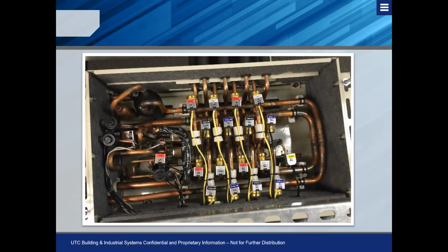If it's something that's caught up in the solenoid, not operating properly from the internals, that's a different story. But if you have an issue with that coil trying to open or close that solenoid, all it is taking is one Phillips screw here, taking that off, lifting the coil off the post, sliding the replacement coil on, putting the Phillips screw back, and then plugging in the electrical connection at the board, and that's it. It certainly is serviceable and easy from a contractor standpoint.